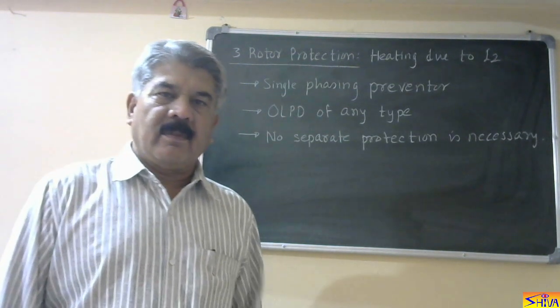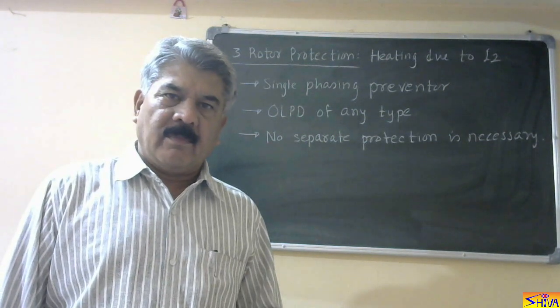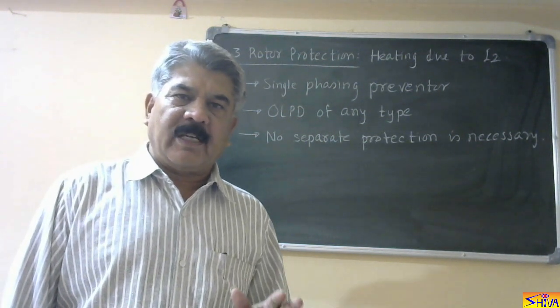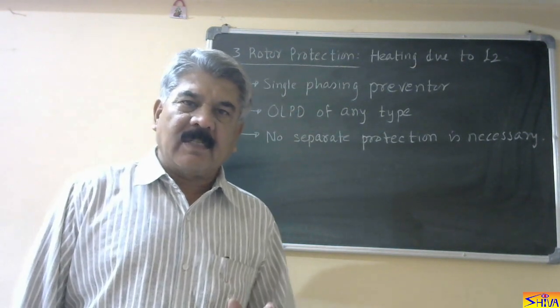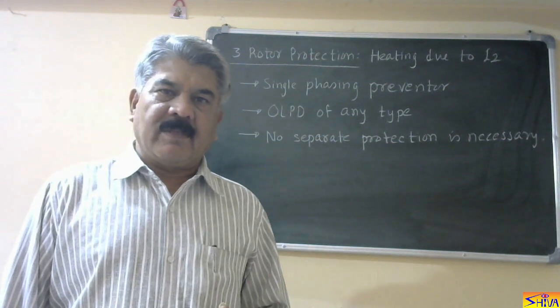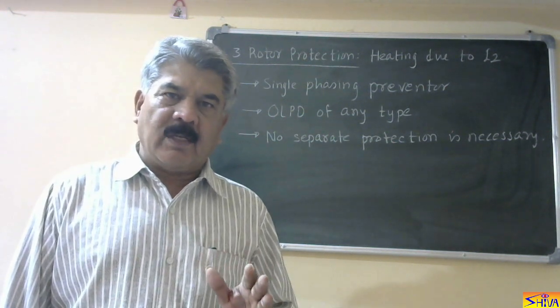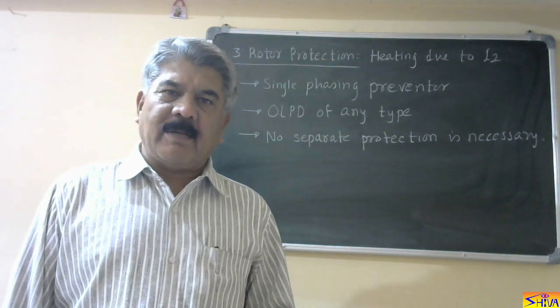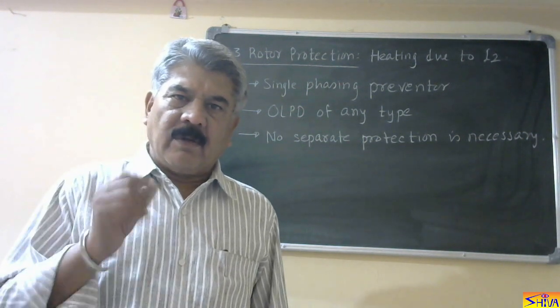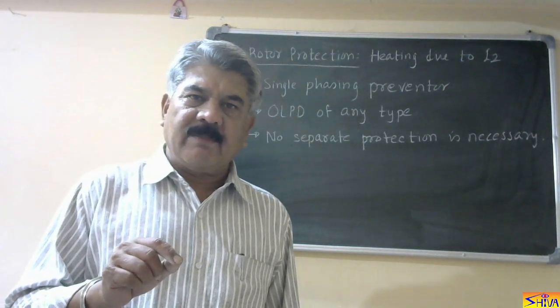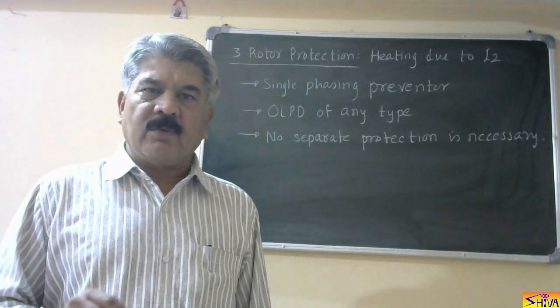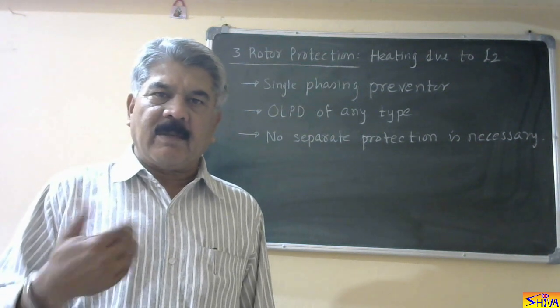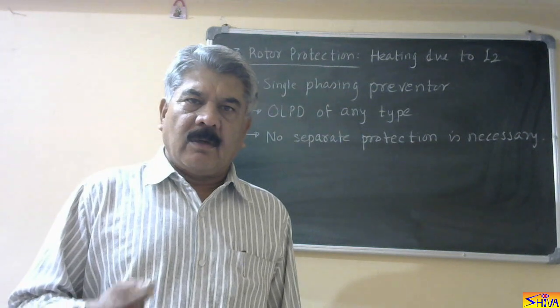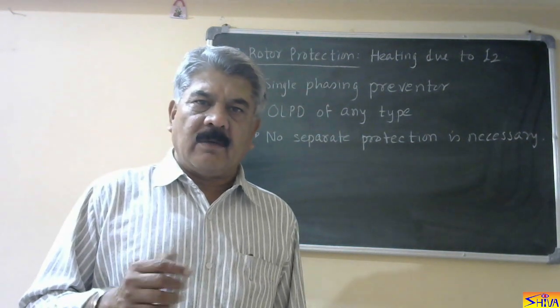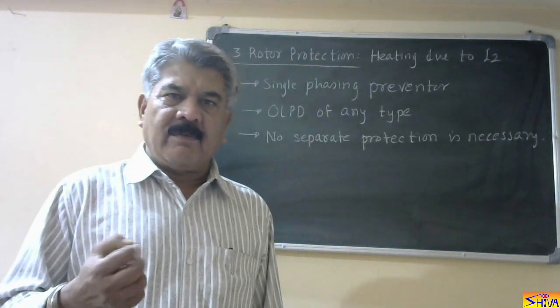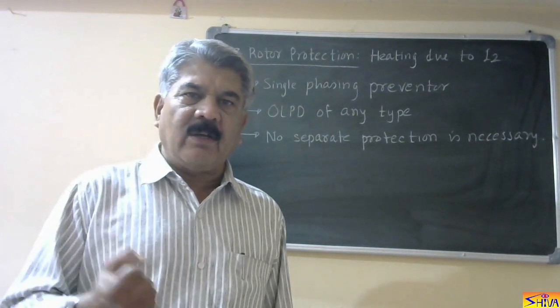In the case of a motor, there is no such thing as a rotor fault, but heating of the rotor takes place due to some reasons. The reasons are unbalanced loading or single phasing. Now, I mean not unbalanced loading but unbalanced supply voltage. When there is unbalanced supply voltage or failure of one phase, in both these conditions, the negative sequence component of the current flows in the circuit. This induces double frequency EMF in the rotor. Due to this double frequency EMF induced in the rotor, whose body is solid itself, current starts flowing, and that causes heating of the rotor.